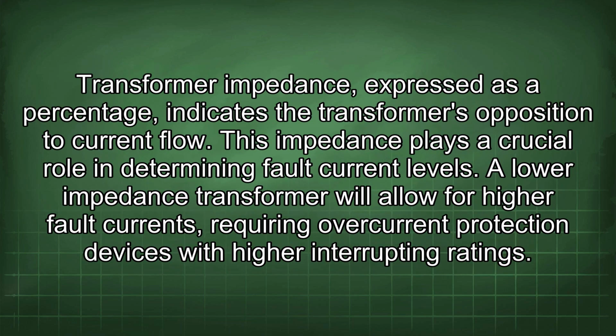Transformer impedance, expressed as a percentage, indicates the transformer's opposition to current flow. This impedance plays a crucial role in determining fault current levels. A lower impedance transformer will allow for higher fault currents, requiring overcurrent protection devices with higher interrupting ratings.